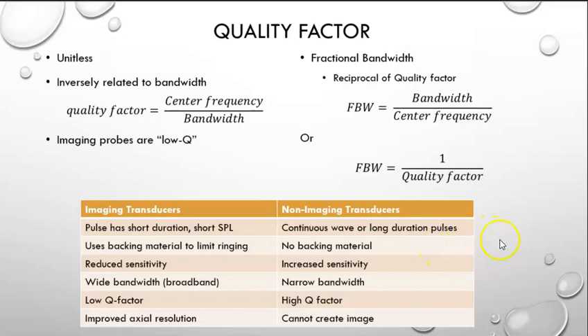There is no backing material on a continuous wave transducer. They have very good sensitivity, extremely good sensitivity, so they can use very, very little power to create their information. They have a very narrow bandwidth. In fact, continuous wave has the narrowest bandwidth you're going to find. It has a high Q factor, very high Q factor, and absolutely cannot be used to make an image with these non-imaging transducers.